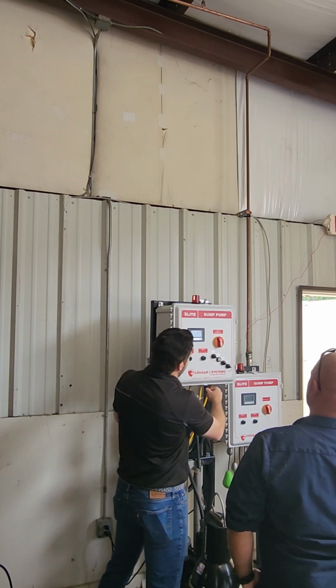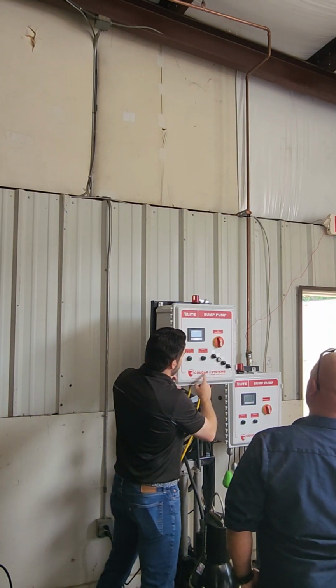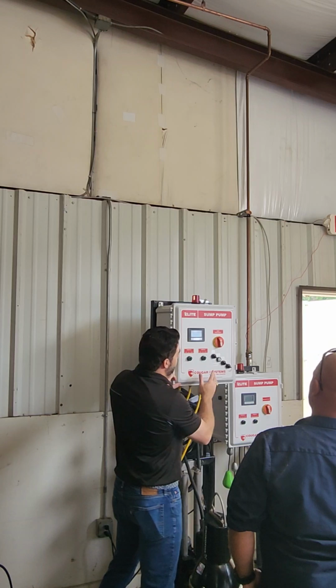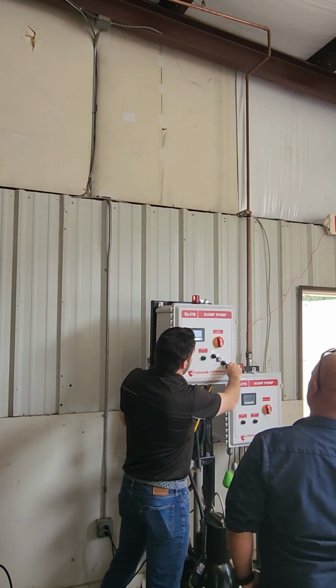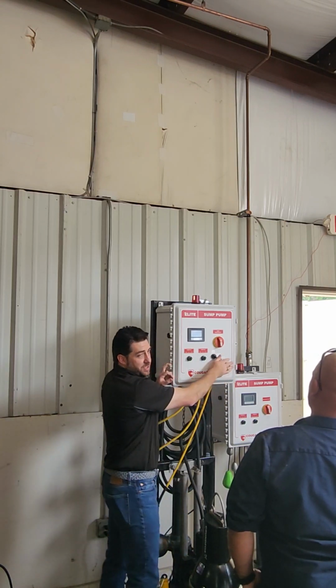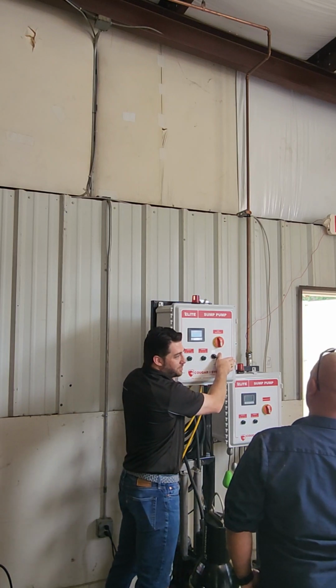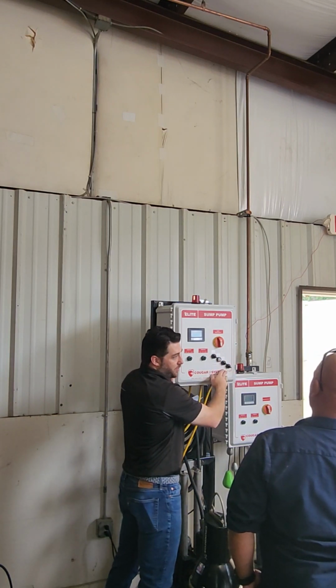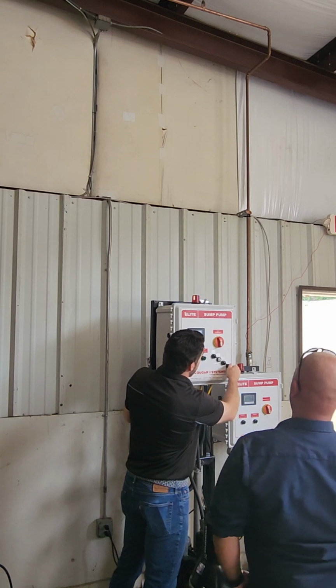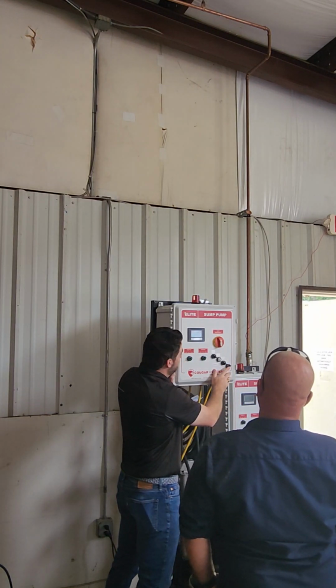Alright, so we'll go through the 4 float switch real fast, and then I can talk through the 2 float if y'all want to see that one. I'm going to use these switches here, just as it's easier than flipping floats. But like I said, you won't see these on a panel out in the field. So the bottom float switch has to come on for the whole sequence to start, right?